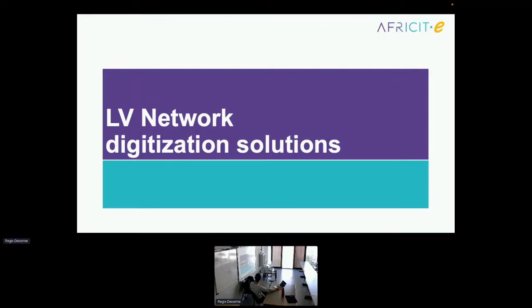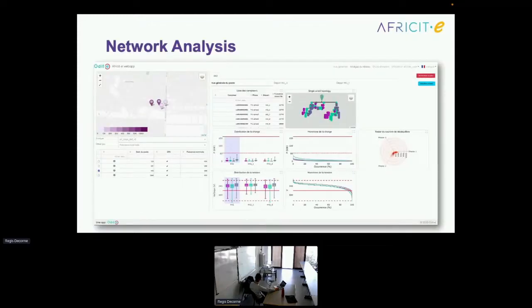LV network digitization solutions: first a network analysis was performed. As I said, for this component we needed the load curve and the voltage profile, and it was not available everywhere, so we could perform it on three different secondary substations. This is Odit-e's work, and based on this data we retrieved the topology of the network: which smart meter is connected to which phase, to which feeder, and to which secondary substation.